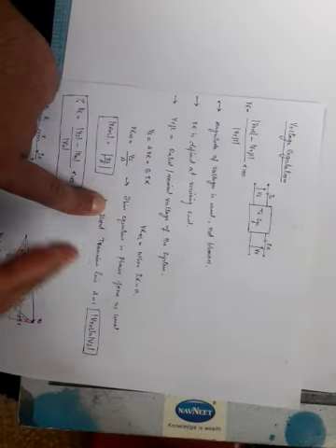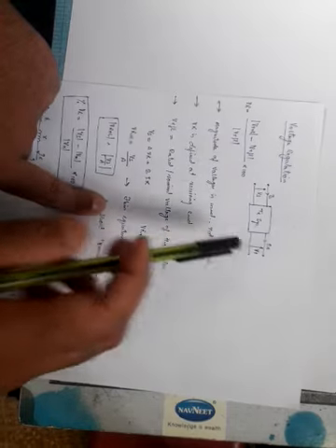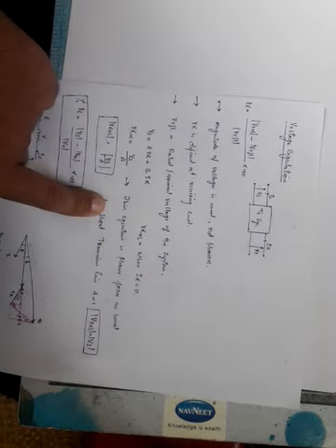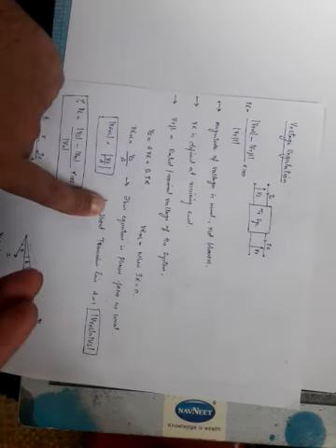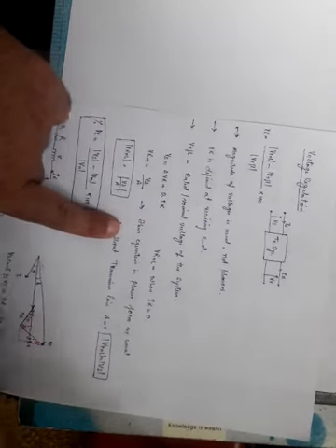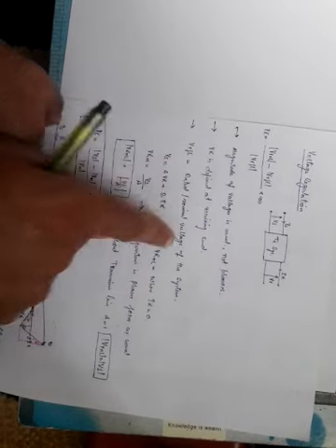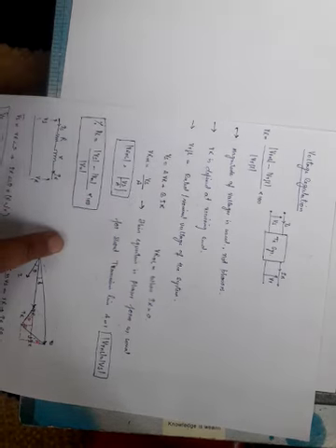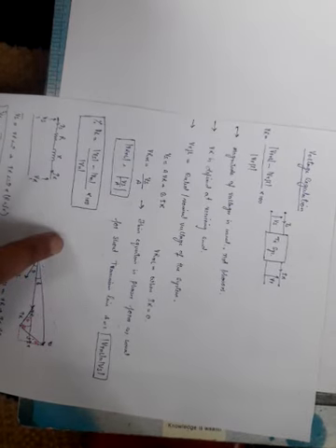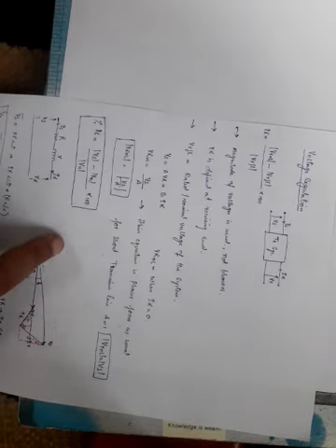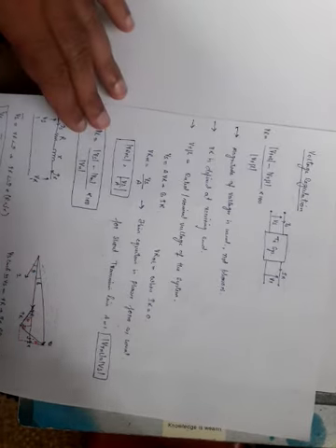And the prime reason is that I have told you that we want a consumer to be supplied the rated or nominal voltage at full load, because at full load there will be the highest voltage dip. At full load Vr should be the nominal voltage. That is why we always take this Vr full as the rated or nominal voltage of the system. We design the system in such a way that the full load voltage comes out to be the nominal voltage, because our power system mostly, if not all the time, works at full load. So all the gadgets get their rated voltage, and when they get a rated voltage, they give their best performance.